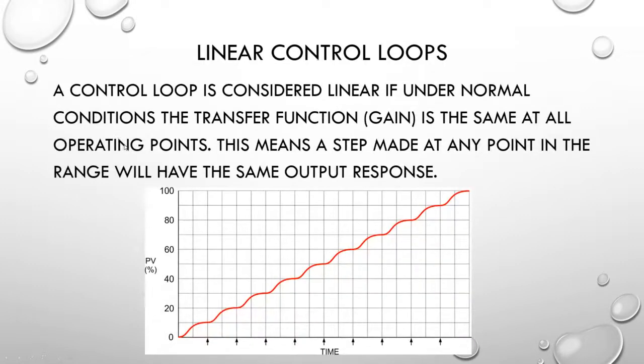We'll start out talking about linear control loops. A control loop is considered to be linear if under normal conditions the transfer function or the gain is the same at all operating points. This means that a step made at any point in the range will have the same output response. The graph shown has 10% input changes, and every step is consistently a 10% output change throughout the operating range from 0 to 100%.